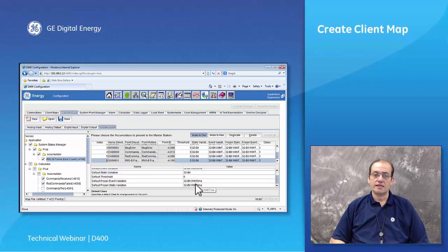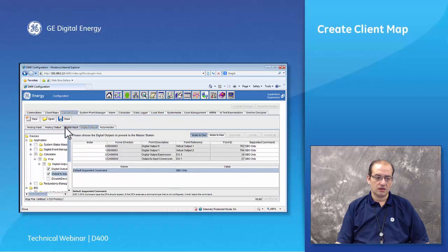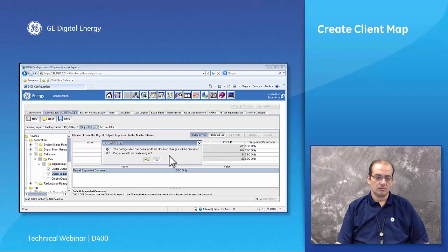That's because when you're configuring a client map under the DNP protocol, you have to specify how often we're going to poll the device and how often the device is going to reply to us. And all of those parameters may not be required in the case of a data processing application or a server map. Okay, so in this case, the server map application that's serving a DNP master does not require that we do any more than these specific simplified parameters.